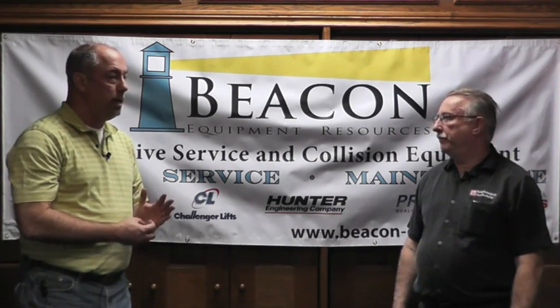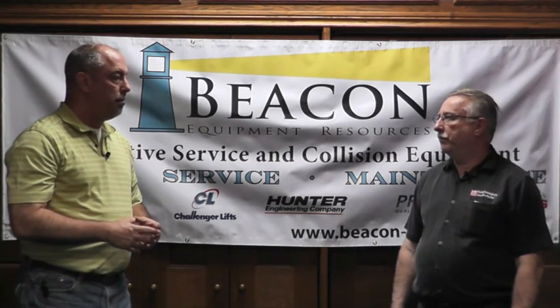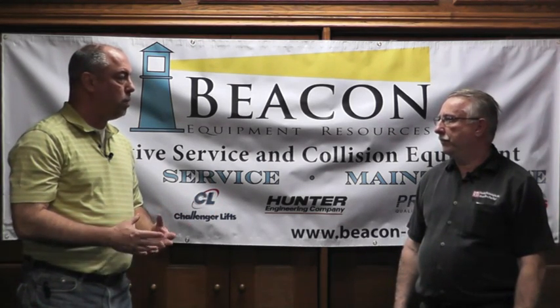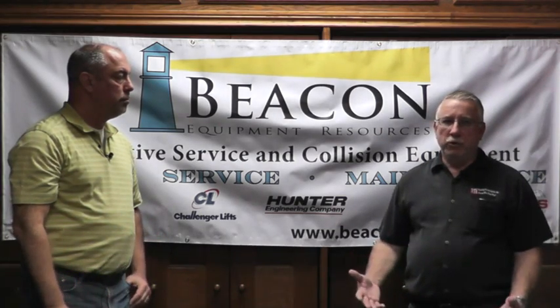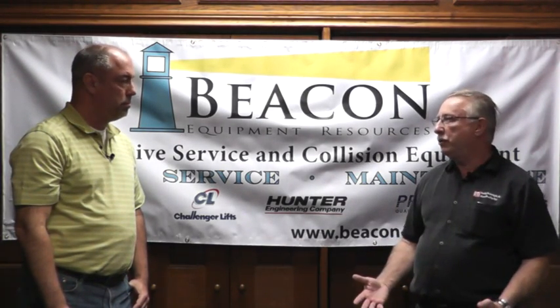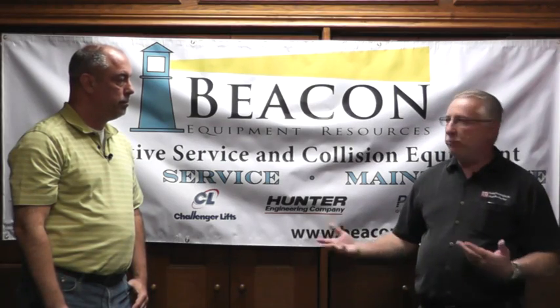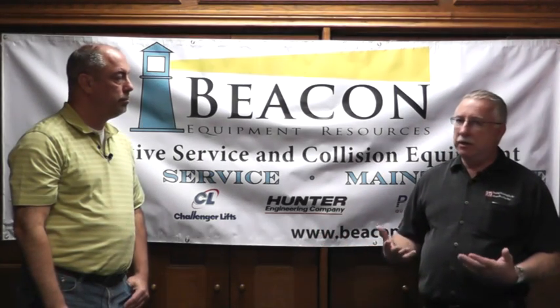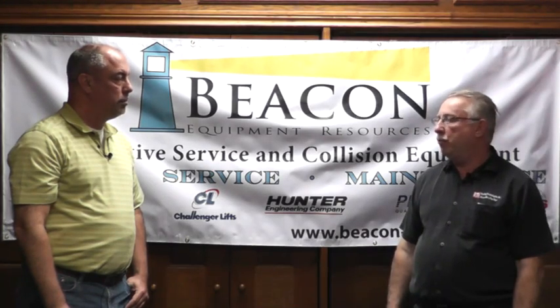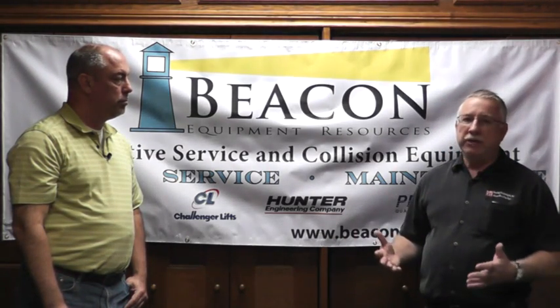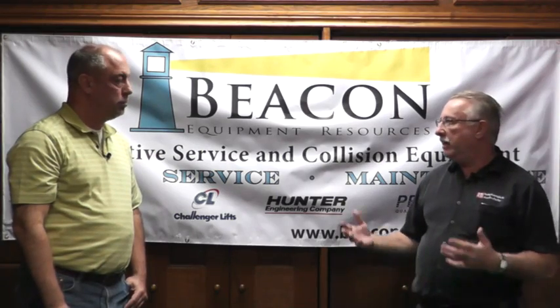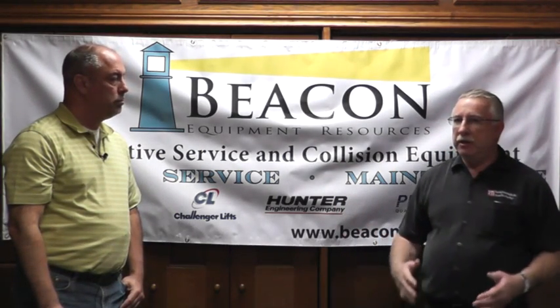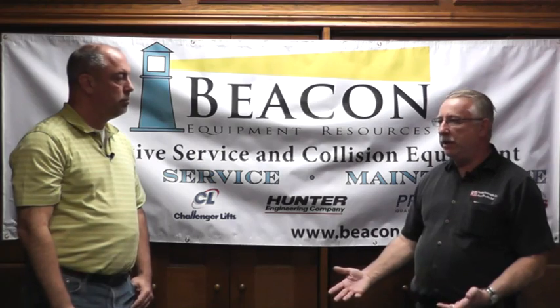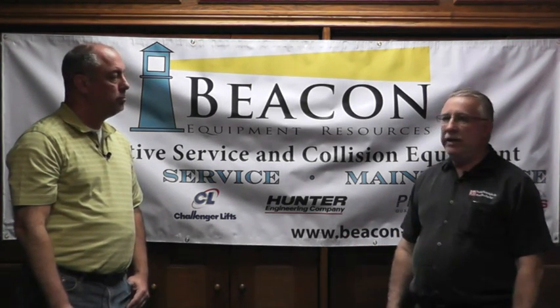Right. But you brought up water, and again that's the big issue that we have. Where does the water come from, and how much water? Compressors work off of air. Air is brought in through the inlet, and the higher the humidity, the more water is going to be produced. For example, we're in Houston here. When it's highly humid, there's going to be a lot of water, and as it's compressed, the water gets entrapped in a vapor, and as it condenses out and goes down line and cools down, it turns to a liquid basically, and that's where the problems occur.